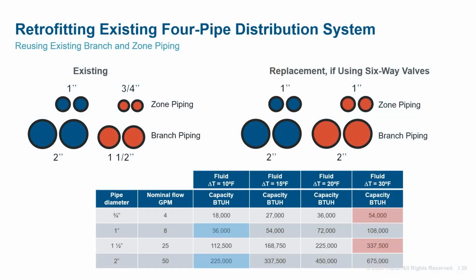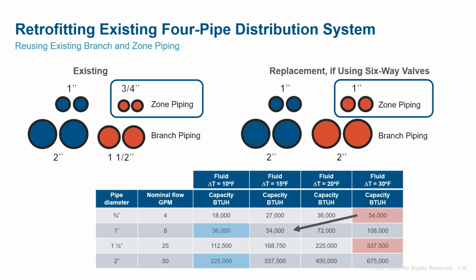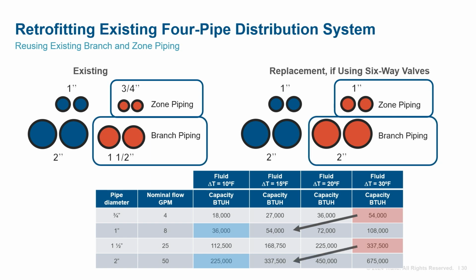The problem with using 6-way valves at each zone is that the existing hot water branch piping is sized for a 30-degree delta T and is not able to handle the added flow required for the same heating capacity. The existing 3/4 inch diameter hot water zone piping needs to be retrofitted to 1 inch for the 105-degree supply water to match heating capacity. And the existing 1.5 inch branch piping now needs to be 2 inches to match the heating capacity. The dual-purpose coil will allow for a larger cooling delta T. The existing piping will be able to deliver additional cooling capacity.